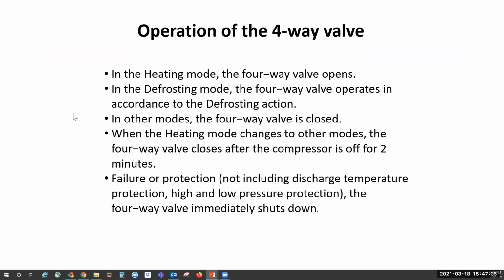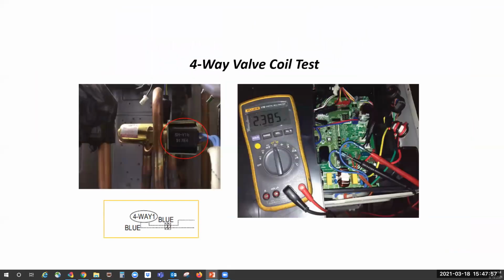Reversing valve or four-way valve. Remember, this is a high voltage, 115 volts or 230 volts, depending on your unit. It is energized in the heat mode. In the defrost mode, it does follow certain algorithms. For testing it, you're going to test it with power on. Make sure you have 0 volts in cooling when it's operating. And when we're in heating mode, we want high voltage, whether it's 208, 230, or 115 volts. If it's not in this range, if it's not getting any voltage to the coil, then you're going to need to replace the control board.